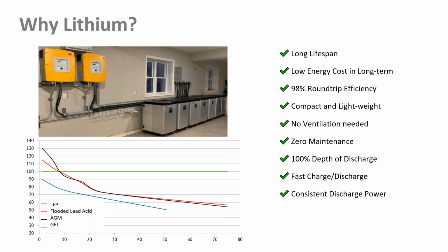Now let's take, for example, the red line, flooded lead acid. Your capacity starts off very high, but as soon as you start pushing out current, your capacity drops rapidly. So what does this mean? This means that when you're sizing a battery, specifically a lead acid battery, and you know you're going to have to push out 50 amps at one point for an electrical load, you're going to have to size it much larger because of that capacity drop as your amperage increases. So, for example, if you needed a 200 amp hour battery bank in lead acid, you would have to get a 400 amp hour battery bank because of the drop in capacity and because you can only discharge at 50%. In comparison, with lithium you could get a 200 amp hour lithium battery because of the 100% depth of discharge, and then you're good to go. So there's no need for oversizing to compensate, because of that main chemistry difference.